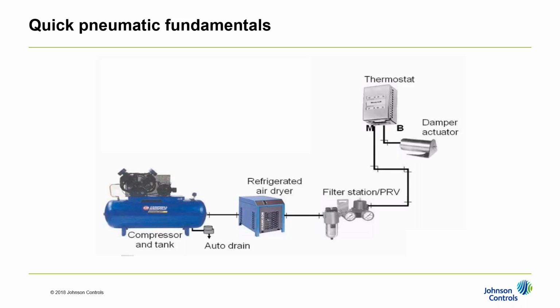It starts with the compressor, which can be a maintenance item in and of itself, but in large part, they work well and last quite a while, and they put out air at typically 70 to 90 PSI. Then they go through some equipment that conditions the air, dryers and filters, just to keep us from pumping contamination throughout our building and through our control equipment. And then once we get to the pressure relief or reducing valve, we're stepping down to 15 to 20 PSI before we get to the controlling device.